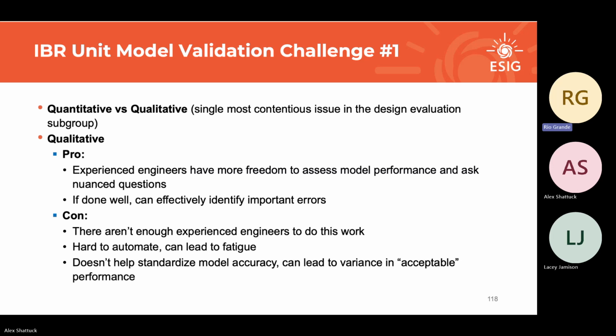And I've had experience doing this on both sides of the fence, and I've had people do it to me as well. As a consultant, you do a model validation quick or do some tests, and you say, well, this looks weird. It's kind of right, but it looks weird. And the manufacturer says, yep, that's a bug. Or I'll be on the manufacturer side and I'll give it to ERCOT, and ERCOT says, this technically passes the requirement, but I'm really curious about this piece of your response. And then I say, oops, and then we fix the bug or fix the performance issue. So it can be a really good tool, but it requires a lot of experience, and mixing the both again can help there. So the con here is there aren't enough of those people around.